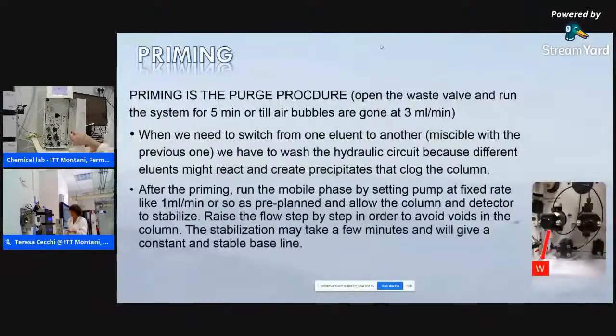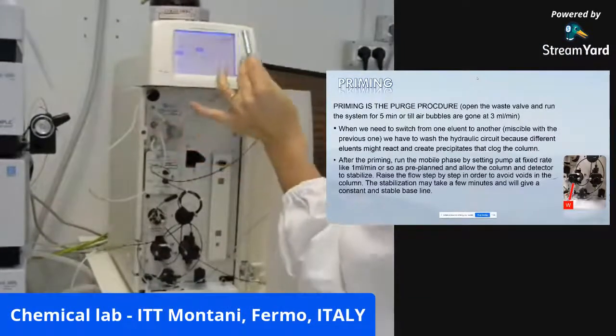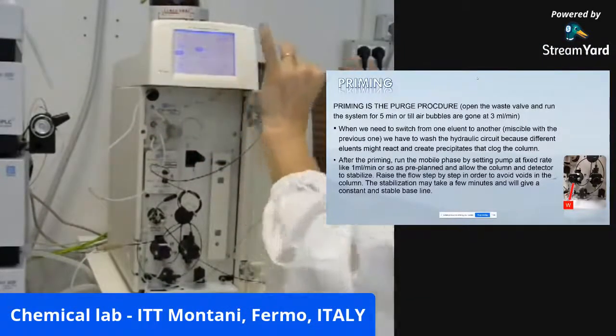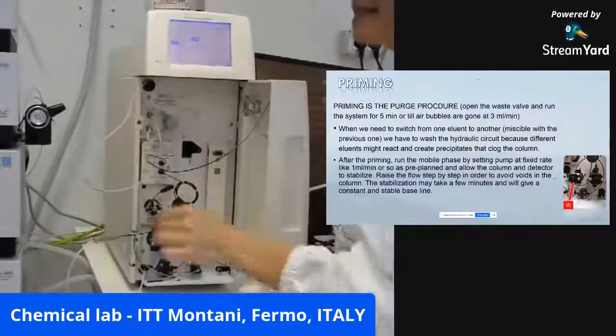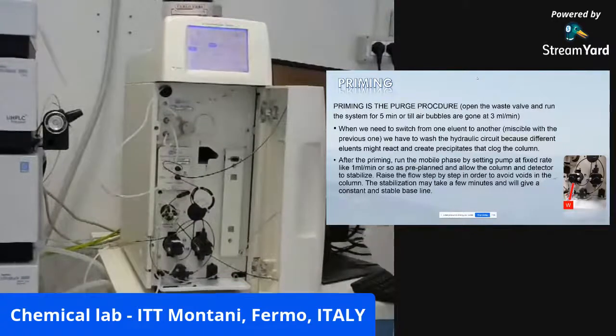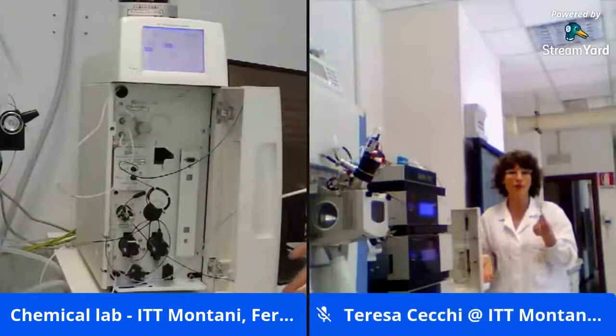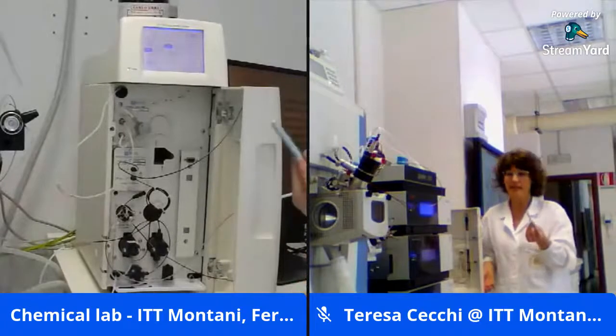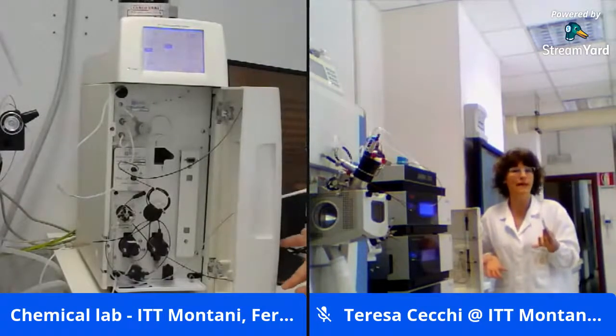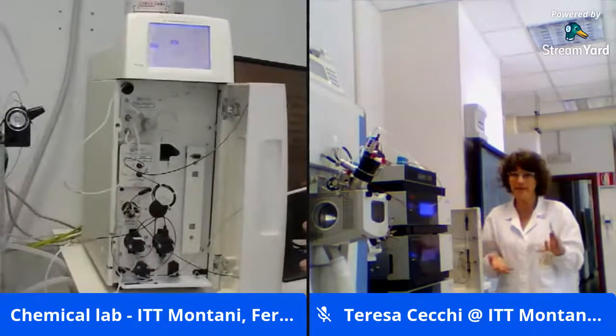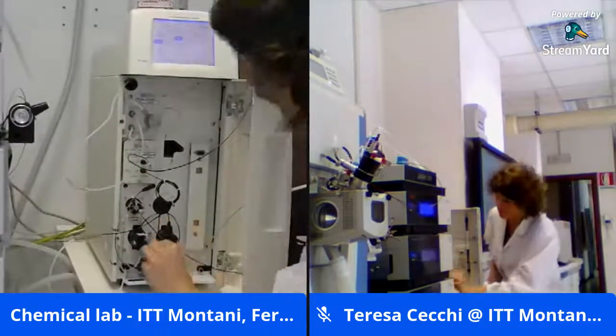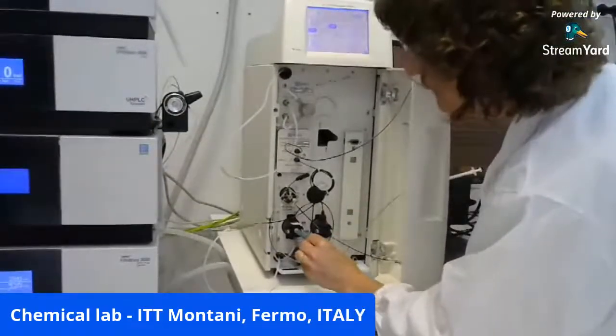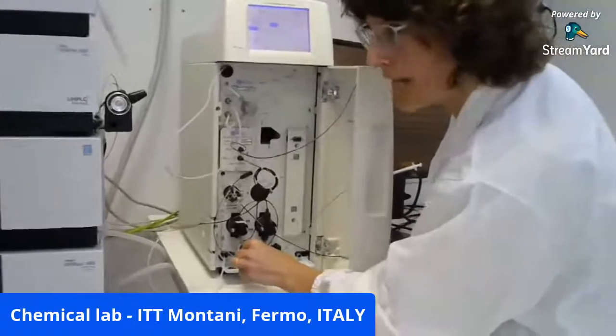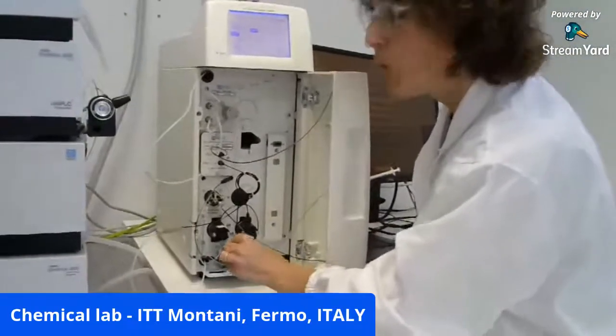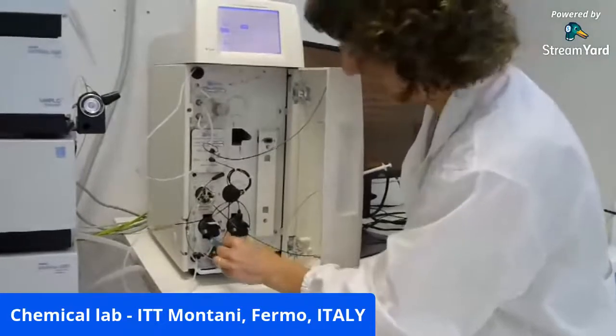Okay, what is priming? Priming is the purge procedure. Well, when we need to switch from one eluent to another, we have to wash the entire hydraulic circuit very quickly. So we have to go, for example, to 3 or 5 milliliters per minute. In this case, such a high flow rate would not be compatible with the column. Hence, we have to open the purge valve and divert the flow towards the waste, just to wash the system very, very quickly.